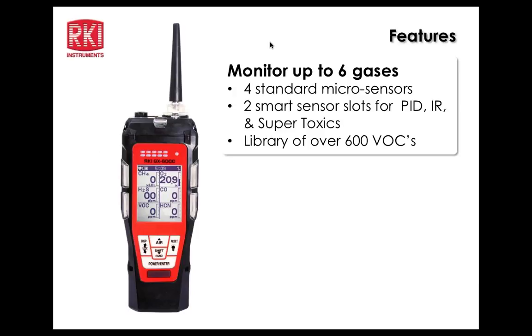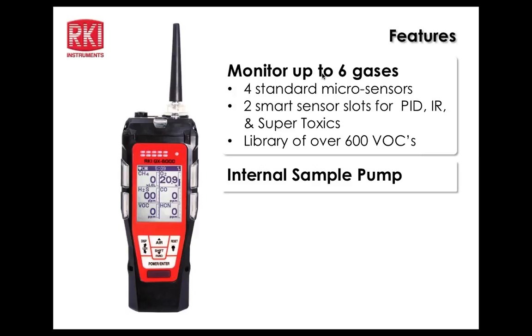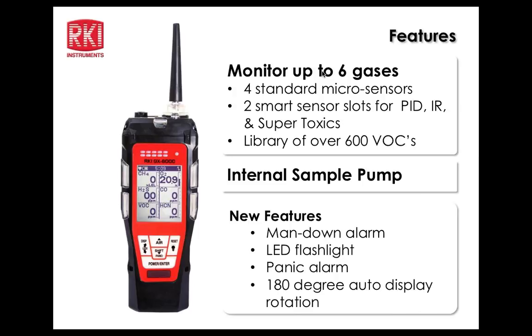Of course, the monitor is up to 6 gases, 4 standard sensors: LEL, O2, H2S, and CO. And there will be 2 smart sensors for the PID, infrared sensors, and super toxic sensors. Okay? And the PID will have a library of over 600 VOCs that can be tapped into and selected and looked at. Obviously, there's an internal sample pump. New features that this unit brings to RKI's offering is a man-down alarm, an LED flashlight, a panic alarm, and of course 180-degree auto display rotation.